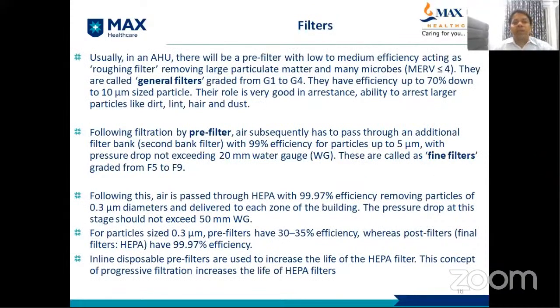Usually in an AHU, there will be a pre-filter with low to medium efficiency acting as a 'roughing filter', removing large particulate matter and many microbes, less than MERV 4. They are called general filters, grading from G1 to G4. They have an efficiency of up to 70% down to 10 micron size particles. Their role is very good in arrestance, the ability to arrest larger particles like lint, hair, and dust.